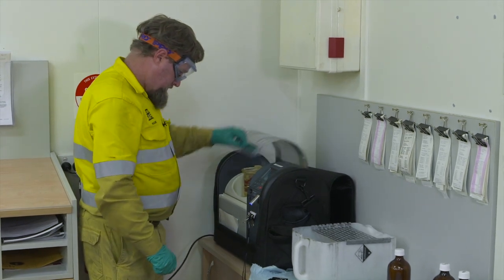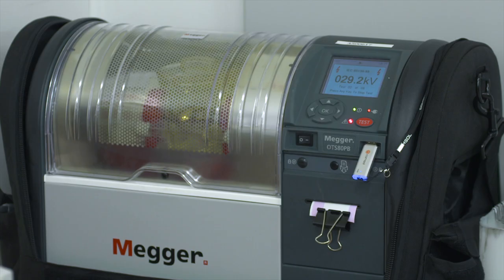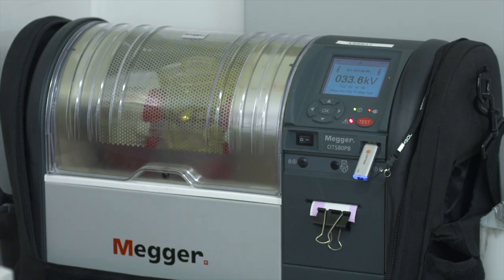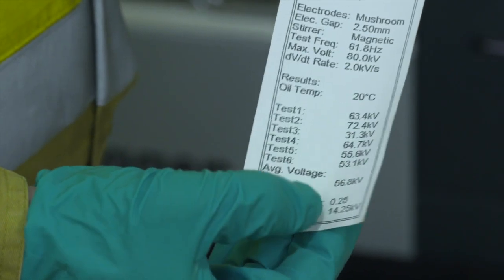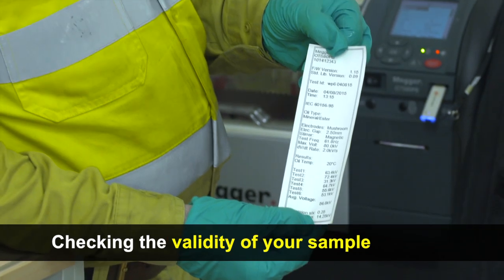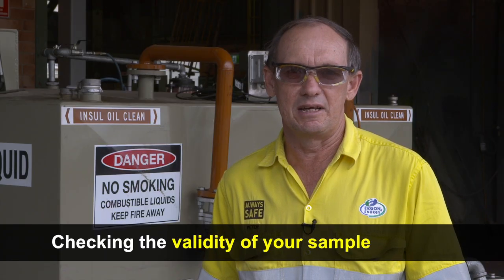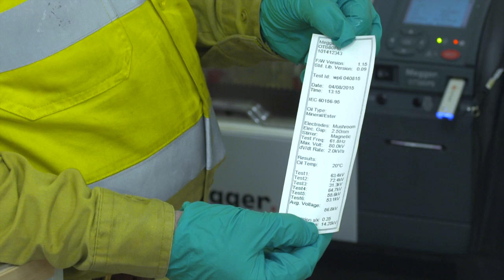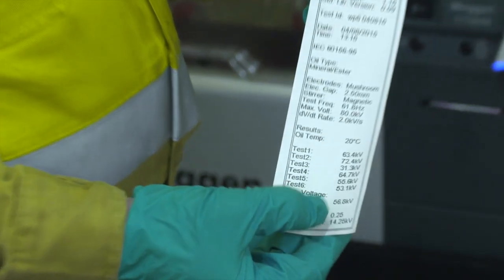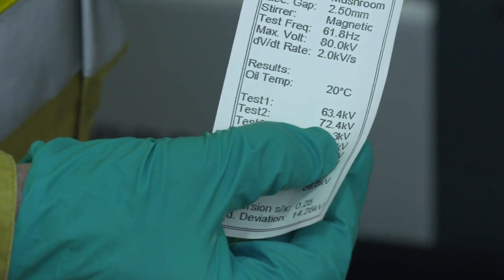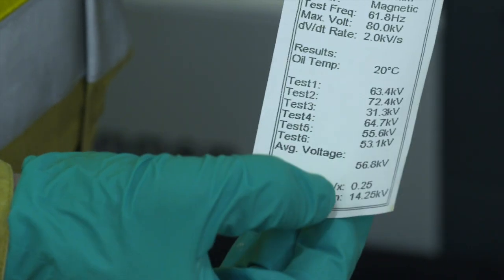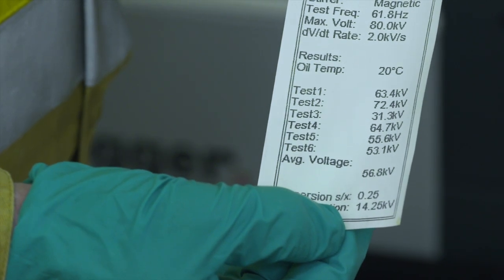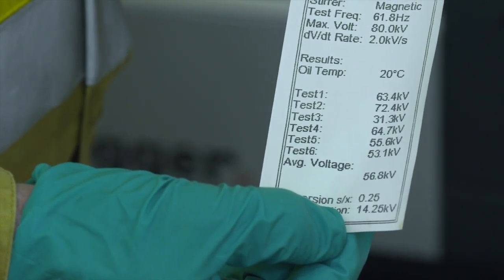When we do a breakdown test on oil, the tester will wind the voltage up and do 6 individual breakdown tests. It will then calculate the average of those and give you a result. There are 2 methods spelled out in the document on how to check the validity of your sample. The easiest way is to look at the average voltage, and if any of the individual test voltages is more than 15 kV away from that average test voltage, then you have to say that you've got a dodgy sample. This may be caused by a number of things.